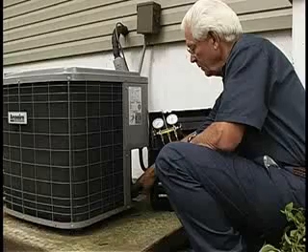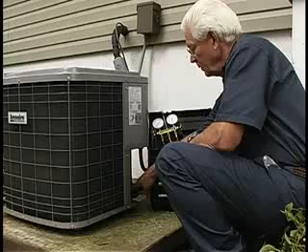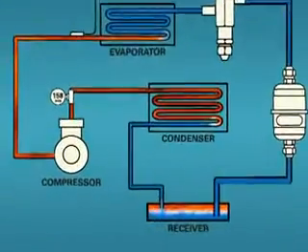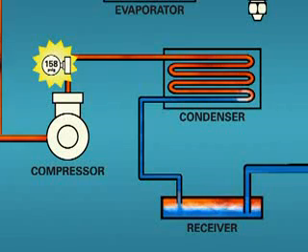So far, in our example, we've been evaluating temperatures and pressures in an ideal type of system. In reality, we don't always get to locate our gauges as we did in this example. Oftentimes, we're forced to make deductions and assumptions. It is often difficult to measure pressure at the outlet of the condenser coil. As a result, the pressure must be taken at the compressor discharge service valve.